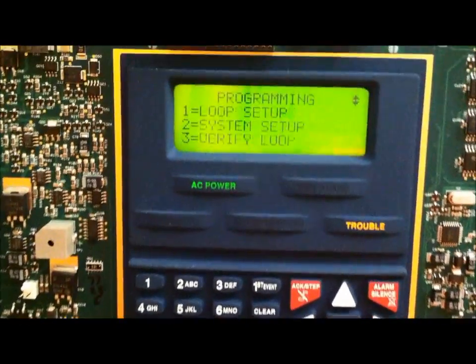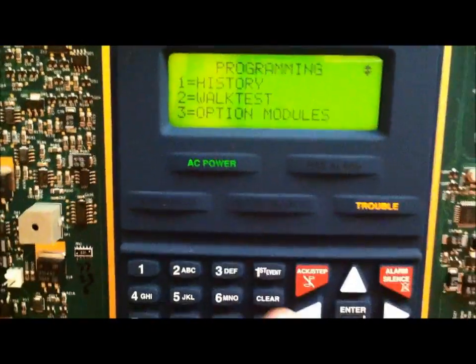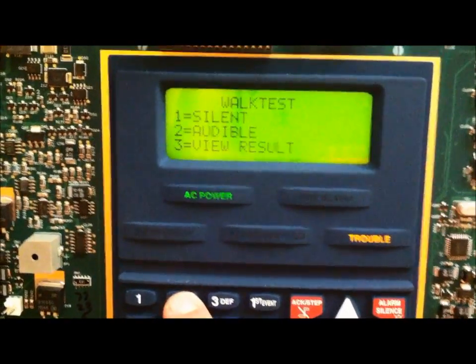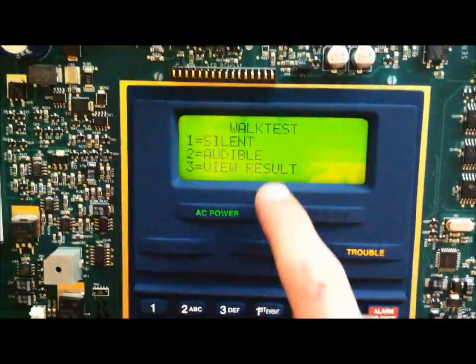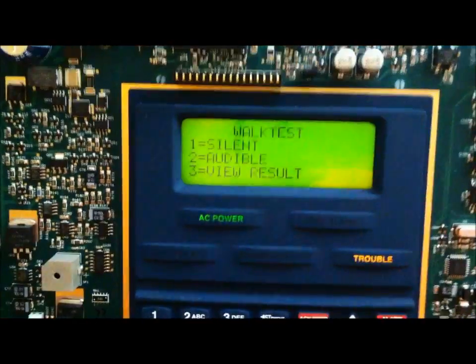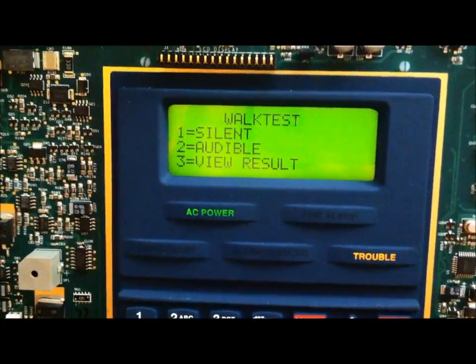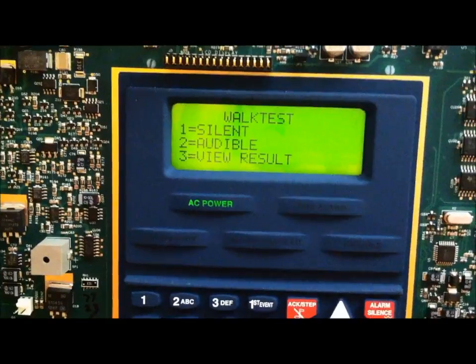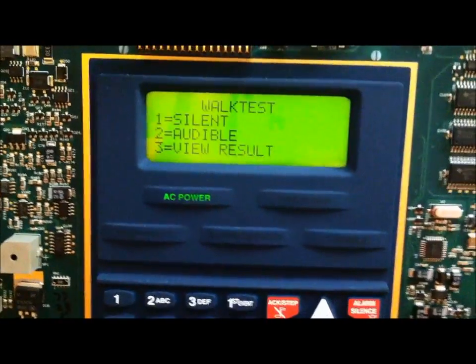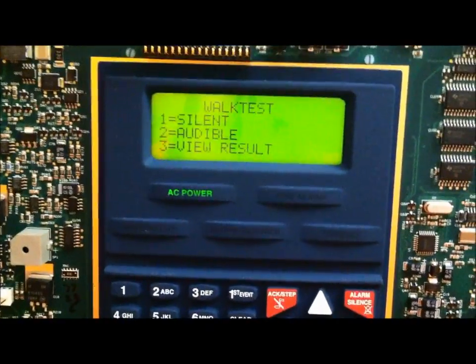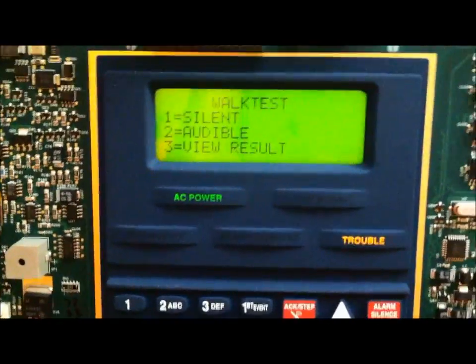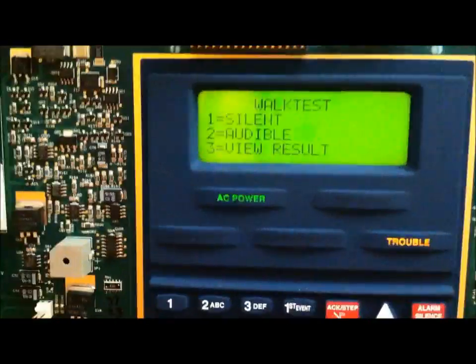We're going to go down to walk tests by pressing 2. There are two different types of walk tests, a silent and audible walk test. With a silent walk test, it does not sound the notification appliances. Whereas, an audible walk test will sound the notification appliances after every device has been activated. When it sounds the notification appliances, it just sounds them for a few seconds after every device.